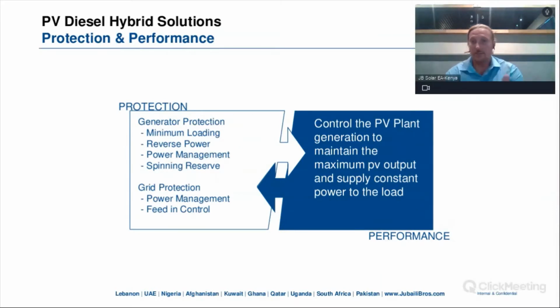So basically there's 2 parts of this. There's the protection and the performance. So the protection is shown on the left. It protects the generator. The fuel save controller protects the generator from minimum loading. And we're going to talk about each of these in the next slides. But minimum loading means a generator cannot be operated below a minimum rating.